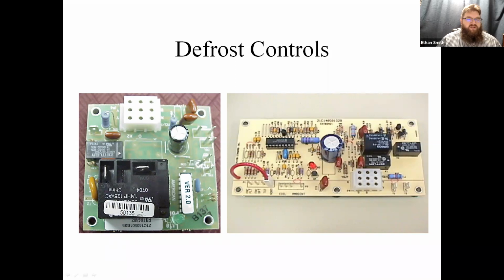There's usually sets of jumpers on here. They're tough to see right here. They're right there. They're marked J1, J2. Sometimes there's a J3. Clipping these jumpers will give you different termination temperatures for your defrost cycle. So humid environments may require a higher termination than a non-humid environment. Depending on your climate or installation circumstance, you may need to clip those jumpers to change your termination temperature. The old generation of boards didn't afford us that always, so that's kind of a nice new feature.